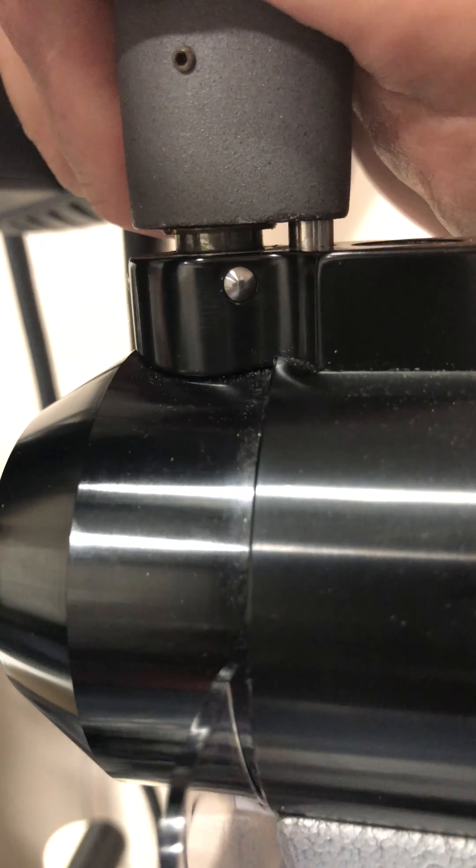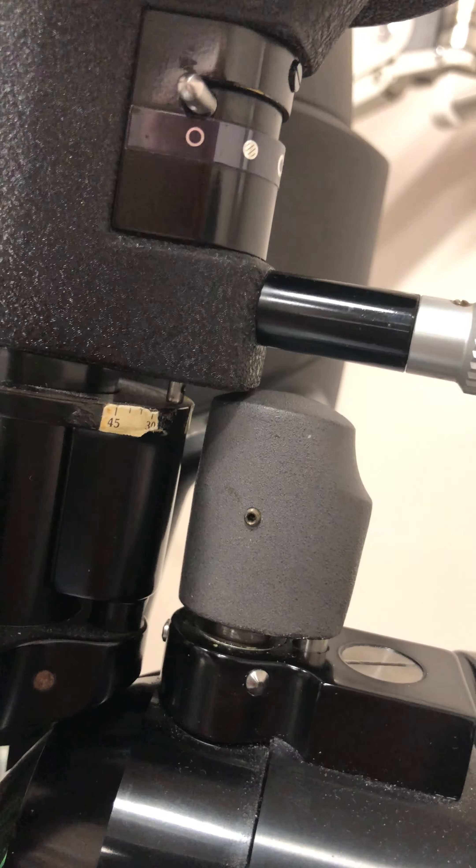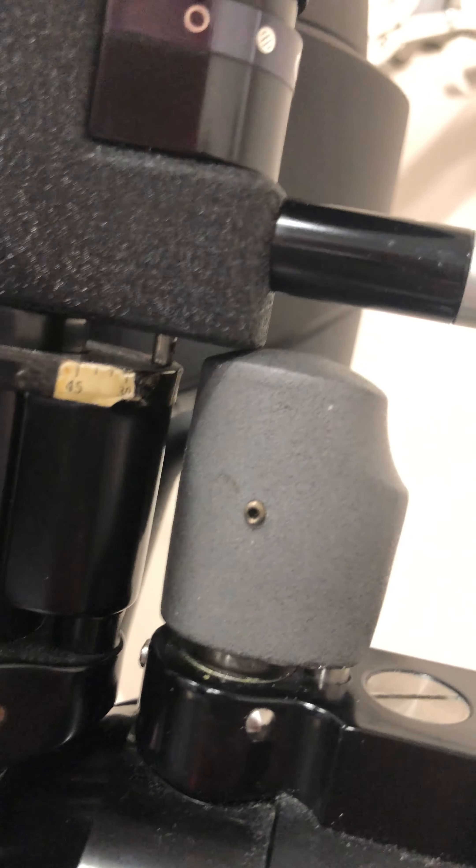The problem we have with the slit lamp: here is the SLT being lifted off the post, and you can see that when it drops into position and engages the pin, there's a pretty good gap between the bottom of the slit lamp and the base of the pin. That's because the pin is one and three-eighths inches long, but the receptacle of the SLT is not deep enough. So what that does is it makes the illumination arm bump the top right there when you swing it over.